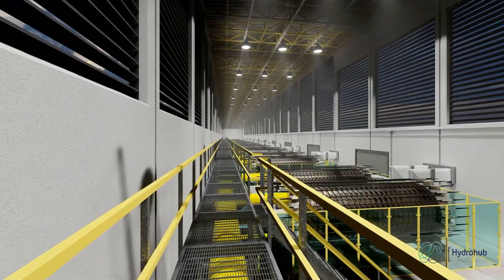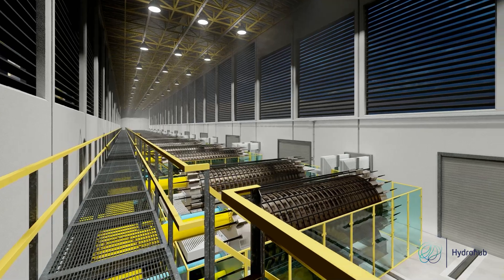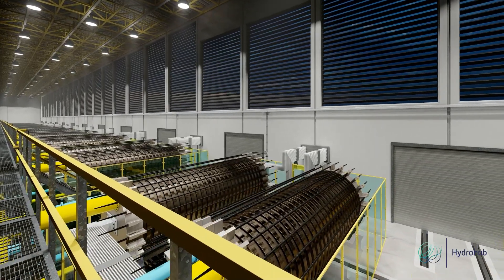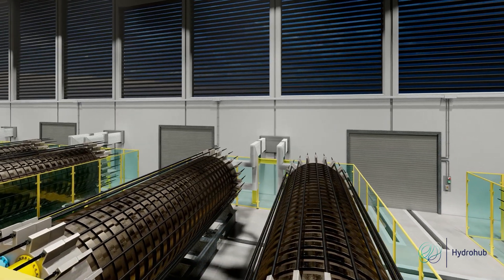The 20 megawatt alkaline stacks have 335 cells at a current density of 1.3 amps per square centimeter. They use high-performance non-noble electrodes and operate at a temperature of 100 degrees Celsius.